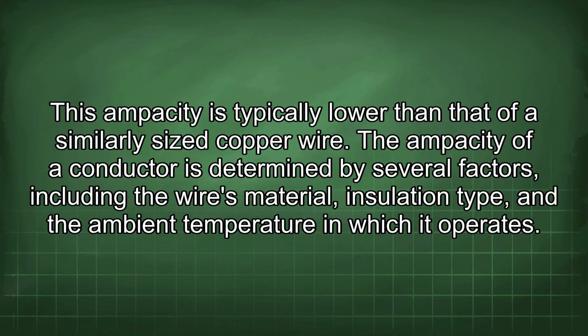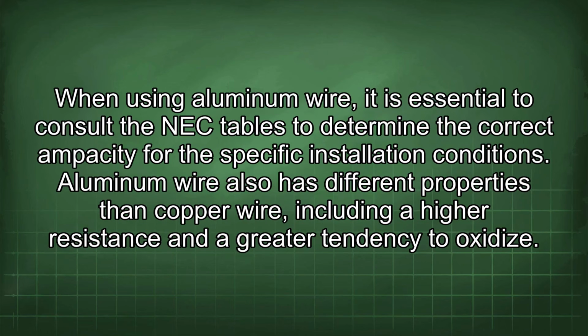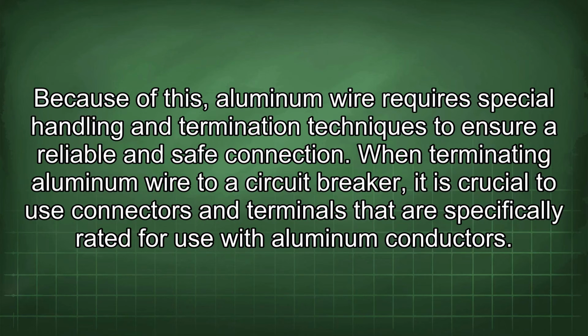The ampacity of a conductor is determined by several factors, including the wire's material, insulation type, and the ambient temperature in which it operates. When using aluminum wire, it is essential to consult the NEC tables to determine the correct ampacity for the specific installation conditions. Aluminum wire also has different properties than copper wire, including a higher resistance and a greater tendency to oxidize. Because of this, aluminum wire requires special handling and termination techniques to ensure a reliable and safe connection.